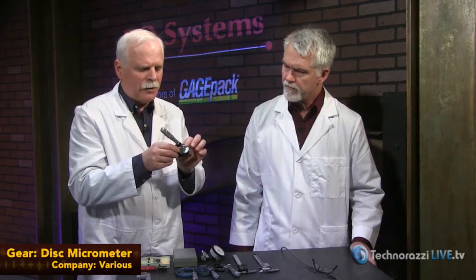The spindle lock uses different methods—friction, ratchet thimble, that sort of thing. Here's a unique type called a disc micrometer. It measures just like a normal OD mic, but the measuring faces are quite large, so it can fit out and measure a flange or something sticking out where the body of a normal mic would hit.